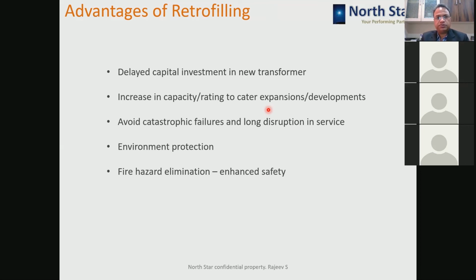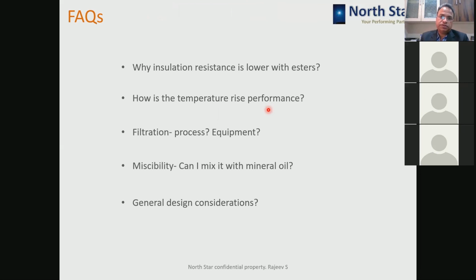Some of the questions: why is insulation resistance lower with esters? As we said, they are a different material altogether compared to mineral oil. They have a polar nature, so you will have some creation of poles inside it. Because of that, your insulation resistance comes lower compared to mineral oil.